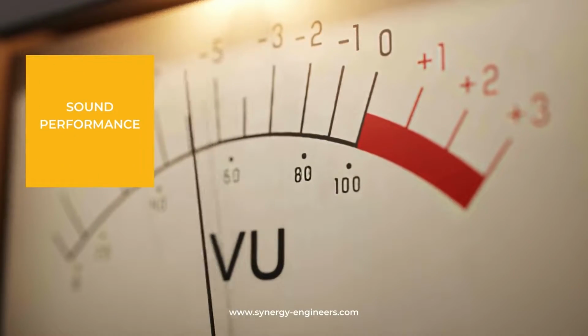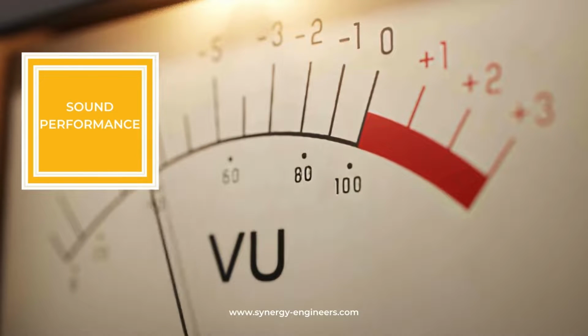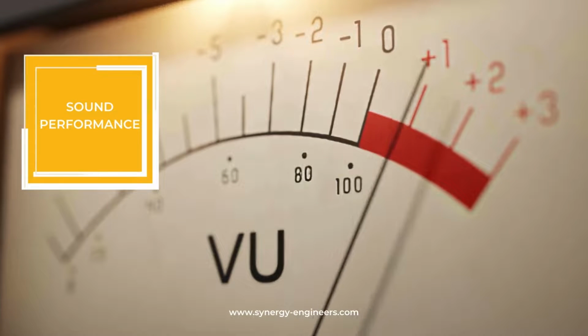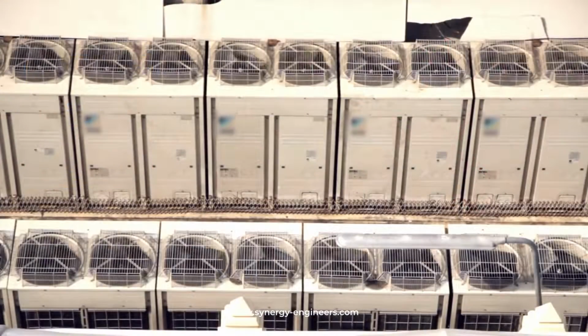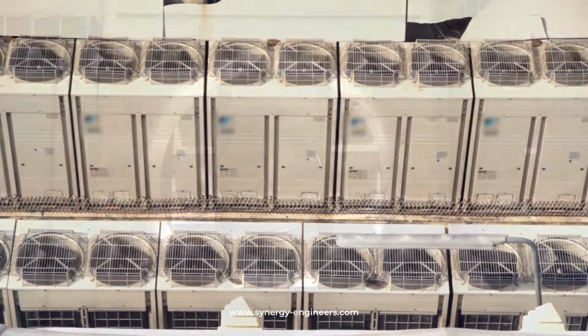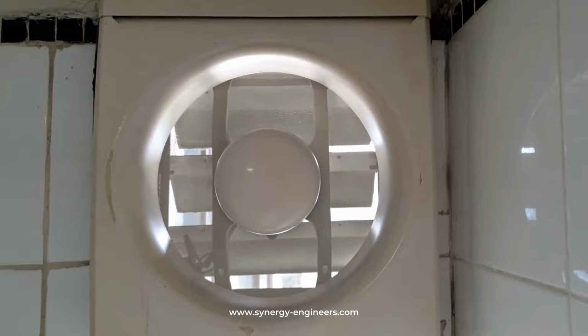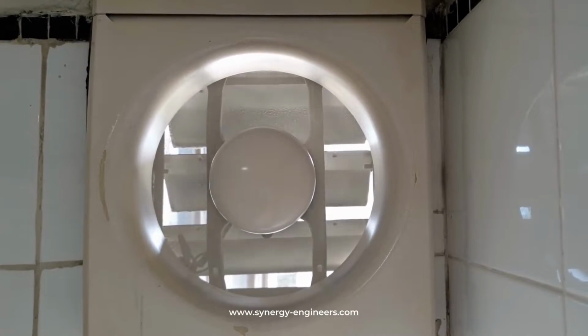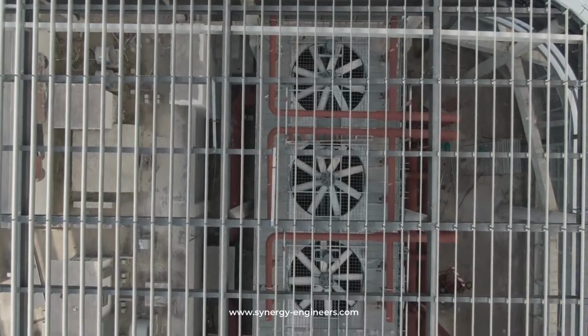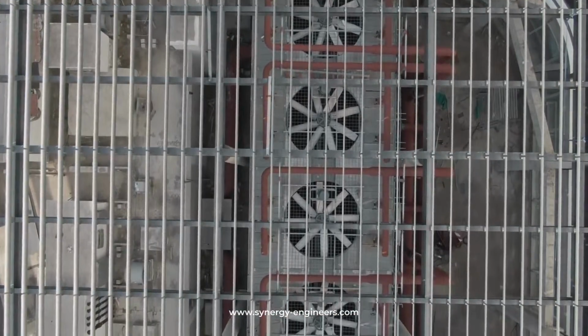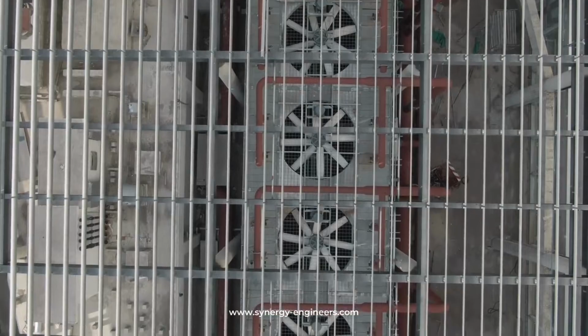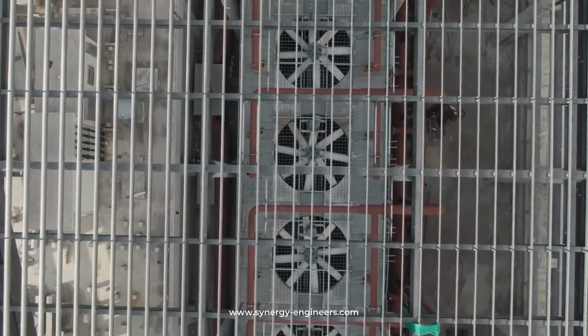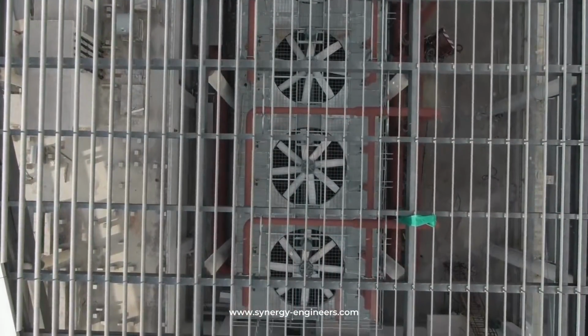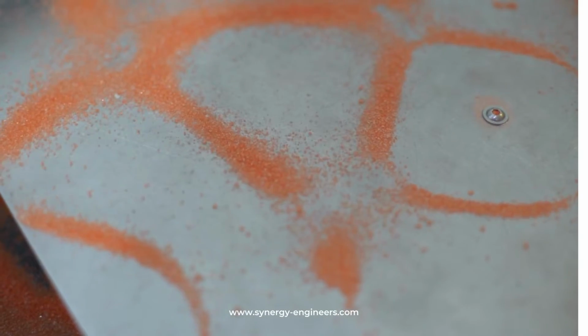So while it may be true that more fans equal more noise, it's important to understand that we're comparing much smaller fans in the array to the old single large horsepower fan. And typically when we look at that, it's basically a wash in terms of the sound performance, and we even get better sound performance with the fan array. Just because fan arrays use fans with smaller impellers, they emit noise in the higher frequency bands, which are much easier to attenuate.